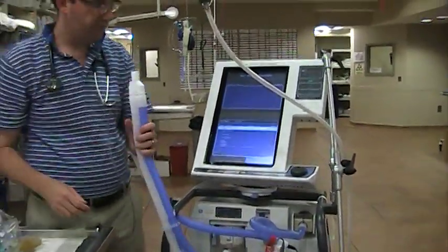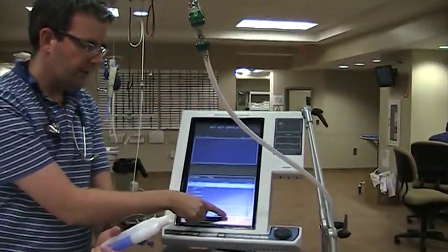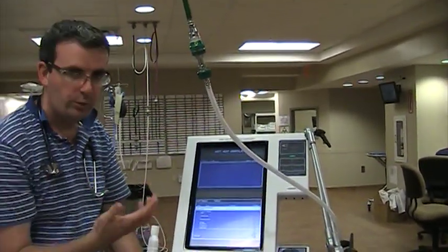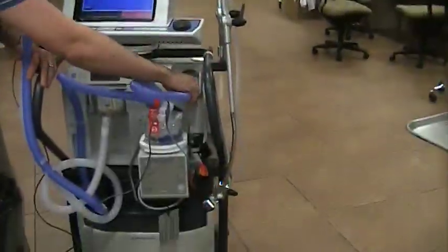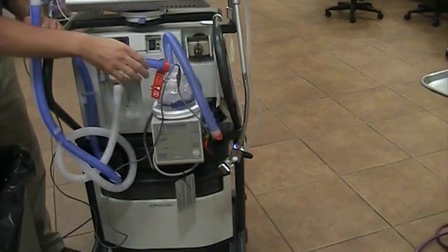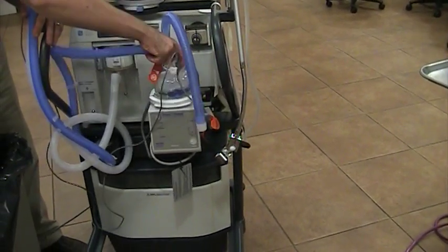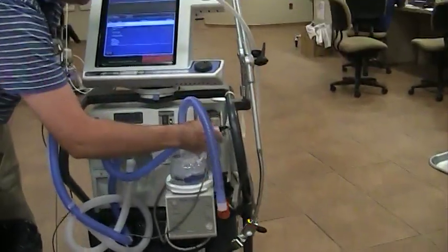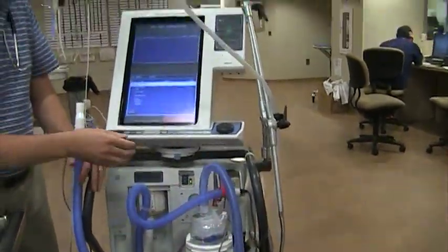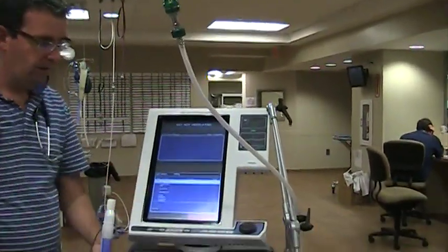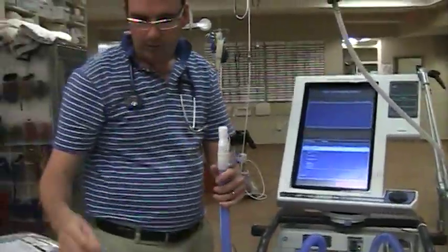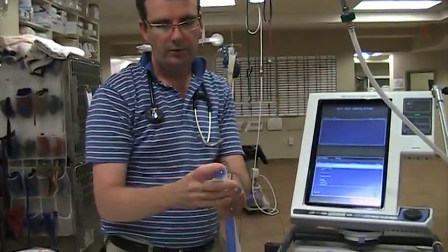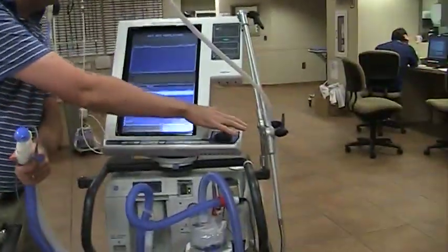So we get to this screen, and it says connect the circuit with the inspiratory filter but without the humidifier. Basically what that means is that we leave the inspiratory filter in, and then we are just connecting the inspiratory line to the filter. And we're bypassing the humidifier for now. And then we say accept. It asks you to block the Y. So this is the Y piece here. So we just block the Y and press accept.